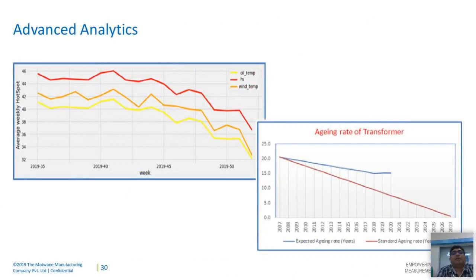So I'll show you some representative images of this analysis on this transformer. You can see the correlation between the winding temperature, oil temperature, and the hotspot. This curve is smoothened out at small instances, and it actually represents the averaged out values over a period of time, typically showing the value over a week's time. If you go to a deeper granular level, you can see the variations happening very dynamically, based on the dynamic loading condition. The other curve is about the aging rate, which takes into consideration the hotspot temperature.